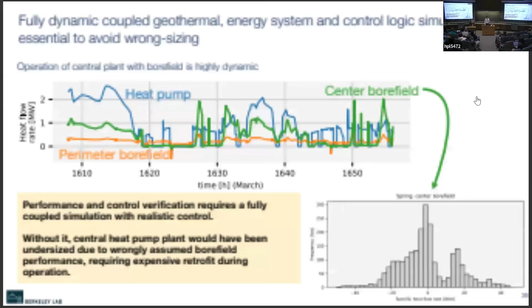We have two bore fields: a perimeter bore field for the daily swings and a center bore field for seasonal storage. You see these large variations depending on whether the bore field is needed to stabilize the loop temperature or whether it's being activated and cooled, for example with the central heat pump. You get these huge changes in heat extraction rates.